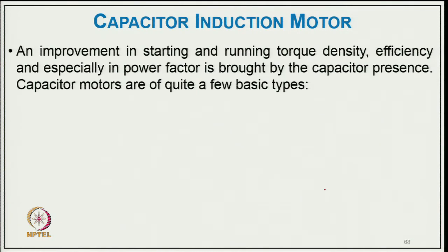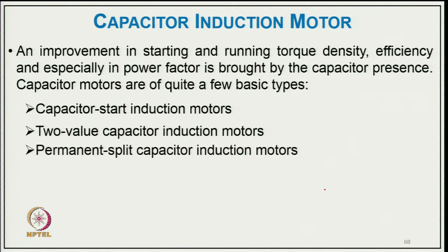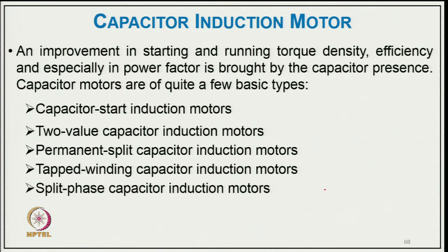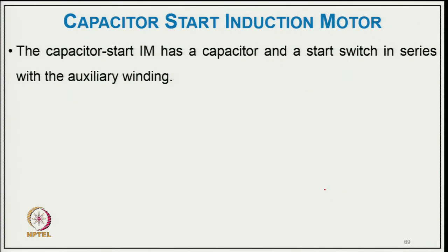An improvement in starting and running torque density, efficiency, and especially in power factor is brought by the capacitor, and capacitor motors are quite a few basic types. Capacitor start induction motor, where the capacitor is only used during starting; then the two value capacitor motor, capacitor start and capacitor run motor; then permanent split capacitor induction motor; then tap winding capacitor induction motor, normally used in fans; then split-phase capacitor induction motor; then capacitor 3-phase induction motor for single phase operation.